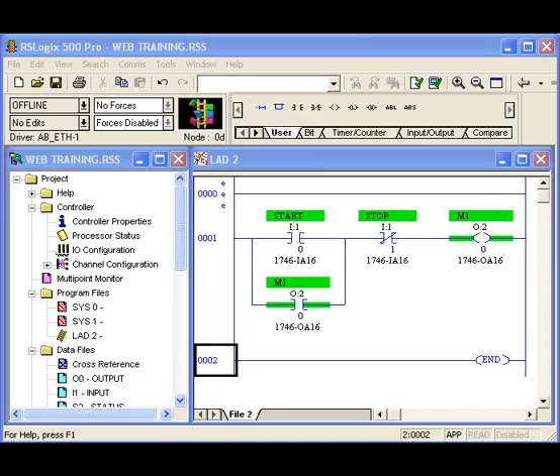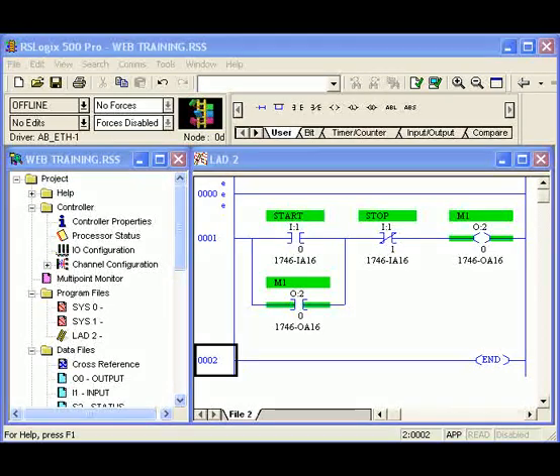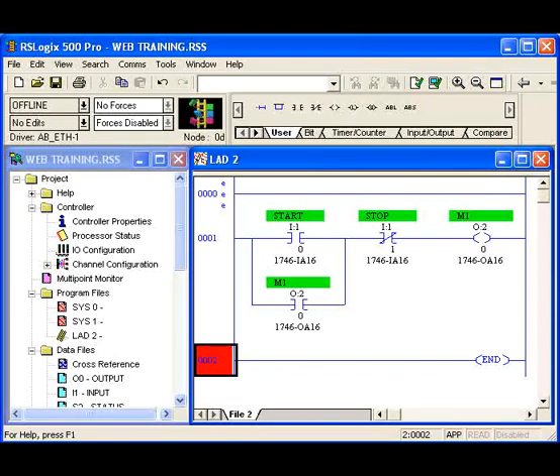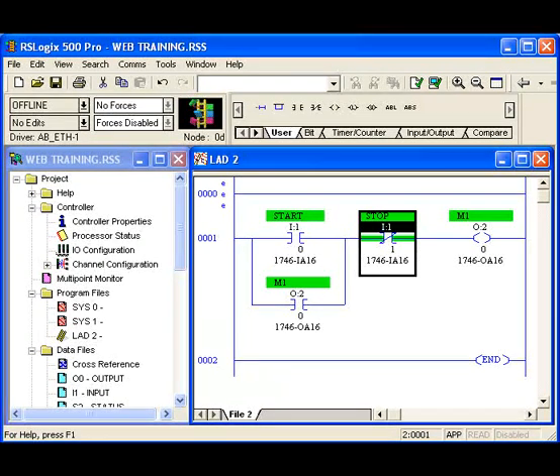So what we have here now is our stop push button is pressed. And you would not have a situation like this in a real PLC where your coil would still be energized with a stop push button pressed. But I'm trying to give you an idea of a very slow motion of how things work in the PLC. So with that stop push button pressed, now the coil has dropped out, the seal has dropped out, and you notice the stop push button is still being pressed because that normally closed contact is off. So now we've ended up back where we started with the stop push button not pressed, start push button not pressed, and the motor is off or the coil is off.